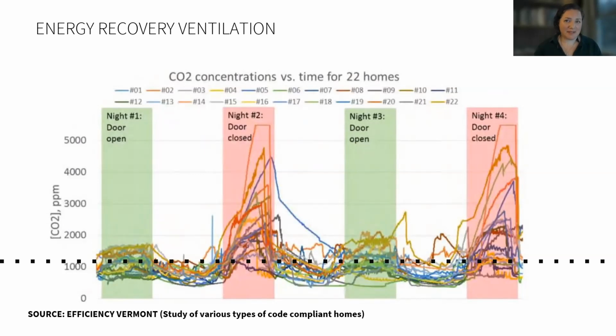So here I'd like to emphasize how critical it is to provide dedicated fresh air to each habitable space through an ERV or an HRV. We are getting more data about how code minimum ventilation is really not providing true air changes or fresh air, even with current energy code minimum air tightness. An example of this dangerous result is CO2 building up at night. Here's the results from one study showing how often it reaches above 1,000 parts per million.